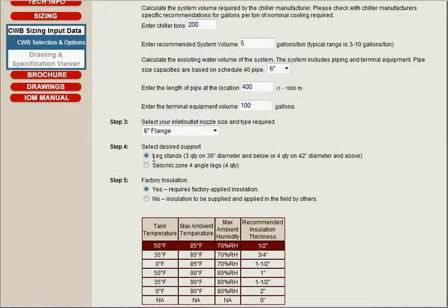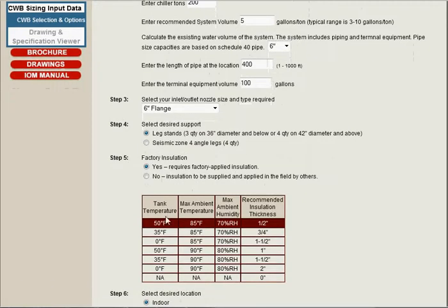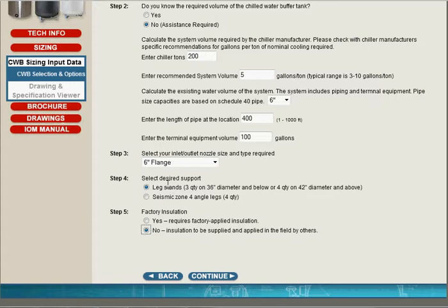Step 4 asks you about the desired support. We're going to leave the default selection of leg stands, noting that you could also select seismic zone 4 angle legs. Step 5 is factory insulation. Down here is a rough chart telling you what the insulation thickness would be. Typical insulation would be 90 degrees Fahrenheit maximum ambient temperature and 35 degrees chilled tank temperature, resulting in a 1.5-inch insulation thickness, which can be done at the factory for your application if you'd like. What we typically do is allow the tank to be insulated in the field, along with the rest of the equipment.